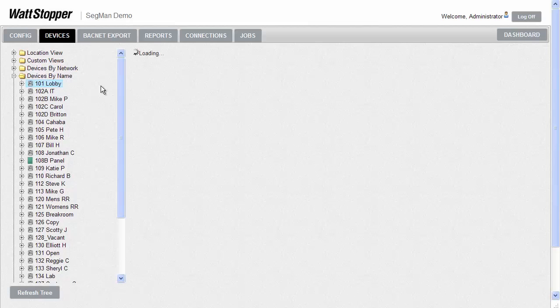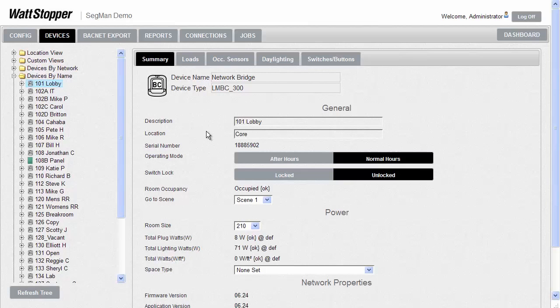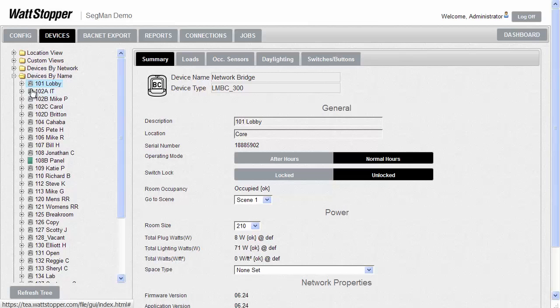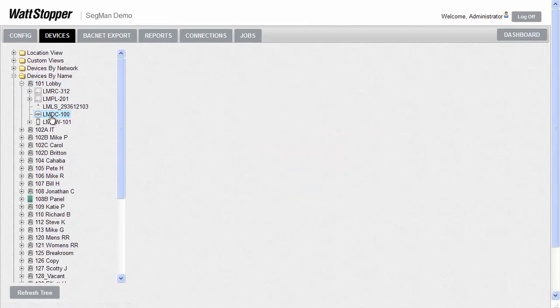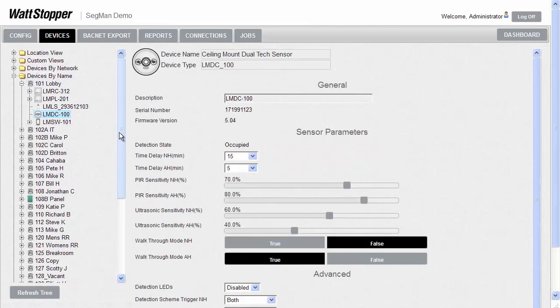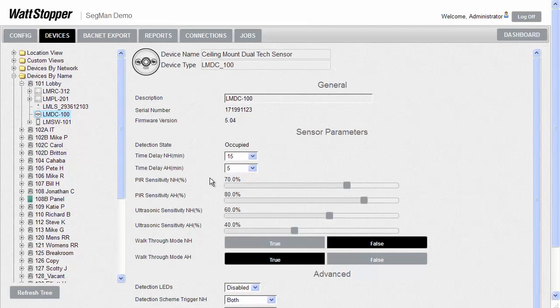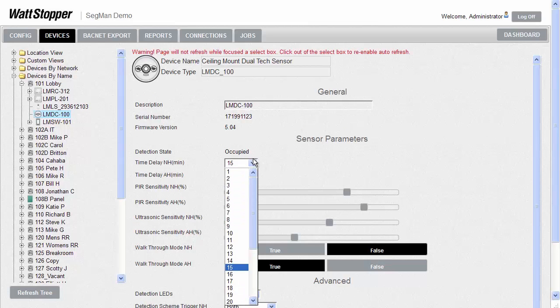So here, this particular room has been labeled 101 lobby and given a location of core. If I expand the info by clicking the plus symbol next to the bridge, you can see the individual devices in that space. Here's an occupancy sensor in that space. And when we select it, we can see its information including the normal hour and after hour time delay setting. By clicking on this drop-down menu, we can change the time delay of that sensor. We can change it from 15 minutes to 10 minute time delay for normal hours.